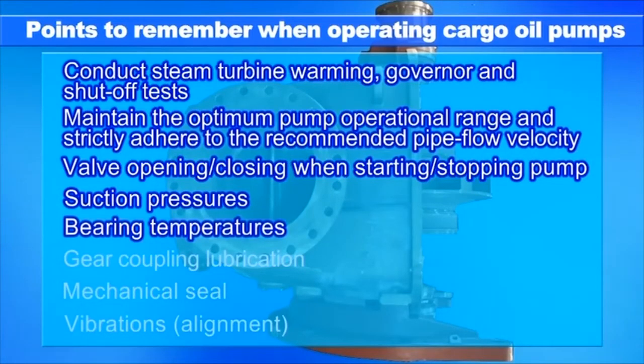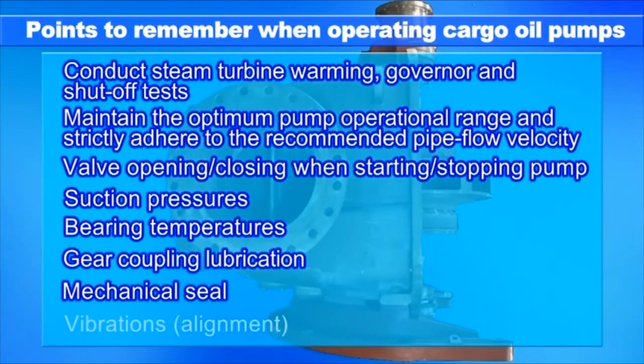Prevent bearing temperatures from rising overly high, check oiling points of gear coupling before lubricating, check leakage from mechanical seal, and beware of vibrations caused by poor alignment.